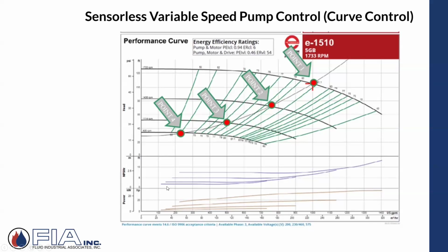What is the flow and head, the corresponding required horsepower to achieve that set of conditions, and then what the corresponding wattage should be to consume at that horsepower, that flow and head. And so as system conditions change, say you're operating out here on the far right at 100% design conditions, and valves close, the first instinct of that pump is to start backing up on the curve. But the variable speed drive logic takes over and says, wait a minute, you're starting to move away from your wattage and your speed. I'm going to back you down, and I have this on board. I don't have remote sensors. I just have this technology on board, and that's why they'll refer to it as sensorless variable speed.